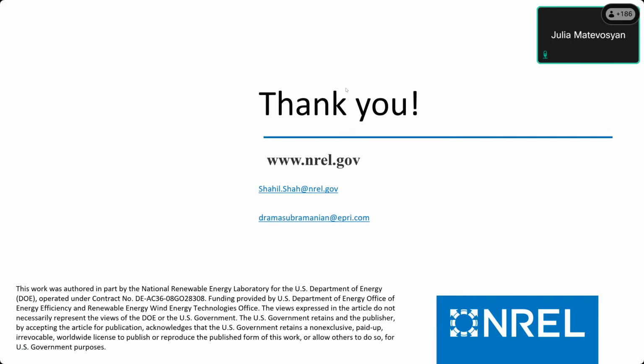The first one is, can those methods be used for validation of EMT models against measurements obtained from testing? Yeah, we did that actually recently for a 2 MVA PV inverter. We presented a paper at the PES General Meeting this year using frequency scans for model validation. So yes, you can use frequency scans to validate the model.